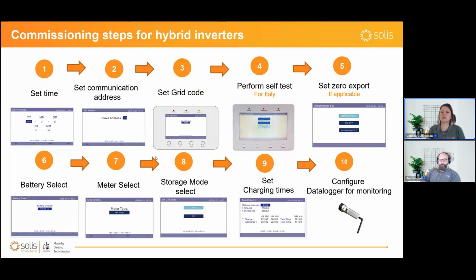Set the time, set a communication address, of course, set a grid code, just like you would do it for the grid-tied inverters. But additionally, you have the battery select. So you have to select the type of battery from the predefined list. You have to select the type of meter, if it's a single phase or a 3-phase meter that you're using. The type of storage modes, if it's self-use or battery reserve, or if you want to set up those charging times, you have to also do that. You can do that as well.